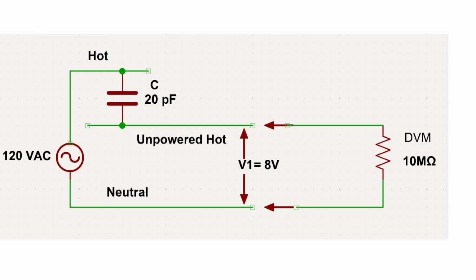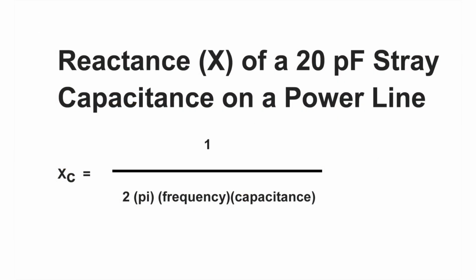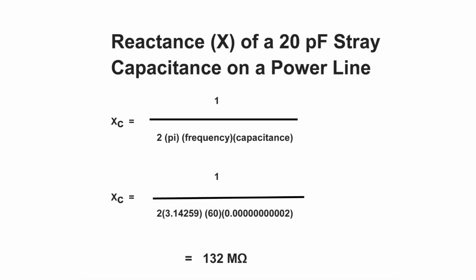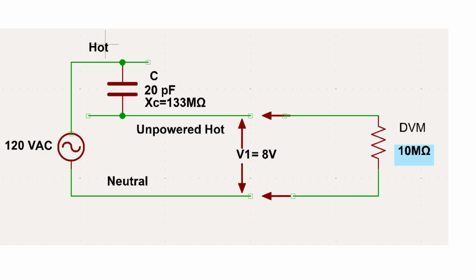short. The property of a capacitance that can be thought of as like a resistor for AC is called reactance. 20 picofarads of stray capacitance has a capacitive reactance of 1 divided by 2 times pi times the frequency of 60 hertz times 20 picofarads, and that's just under 133 million ohms. 133 million ohms is much larger than the input resistance of a typical DVM of 10 million ohms, so only a fraction of the line voltage appears at the DVM.